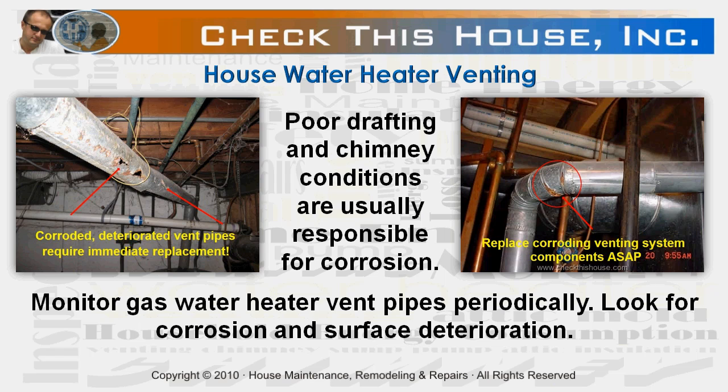The next step is the maintenance routine. You have to periodically monitor vent pipes for corrosion and deterioration. If you notice something, investigate. Draft problems, condition of the chimney, and inadequate amount of combustion air are usually responsible for those problems. Most common areas to look for corrosion are along the bottom portion of the pipes and on connector edges. Once it starts corroding, the vent pipe wall becomes very soft and might fall apart even under slight pressure. Corroding gas water heater vent pipes should be replaced as soon as possible to prevent exhaust fumes and carbon monoxide poisoning.